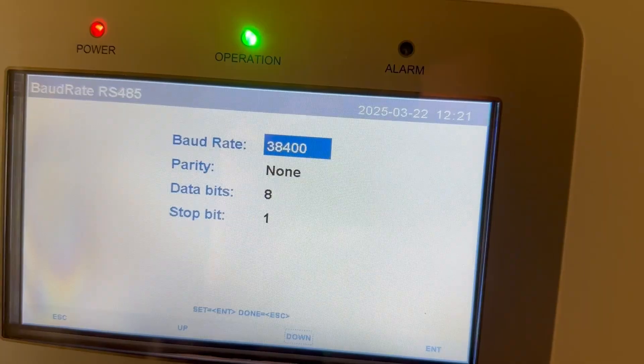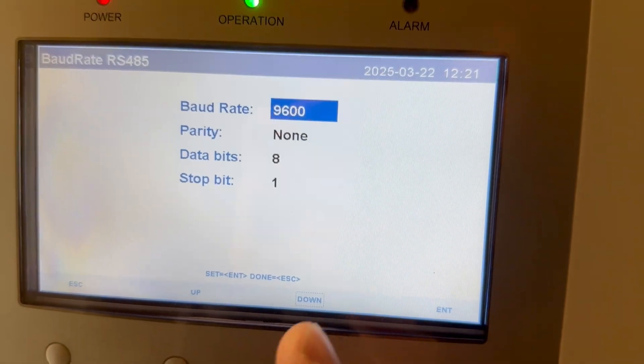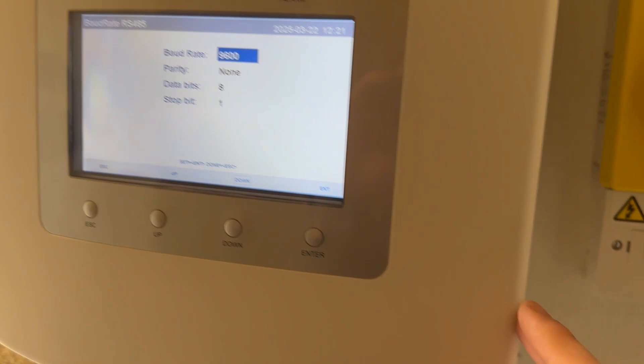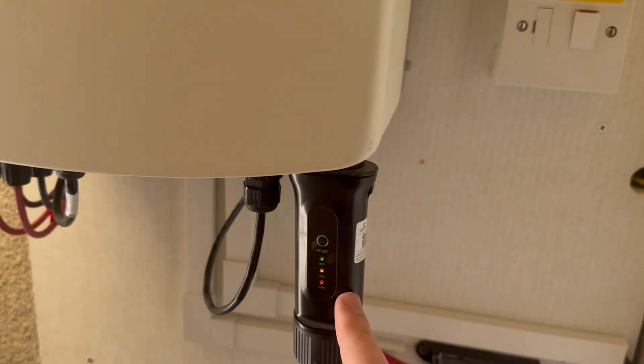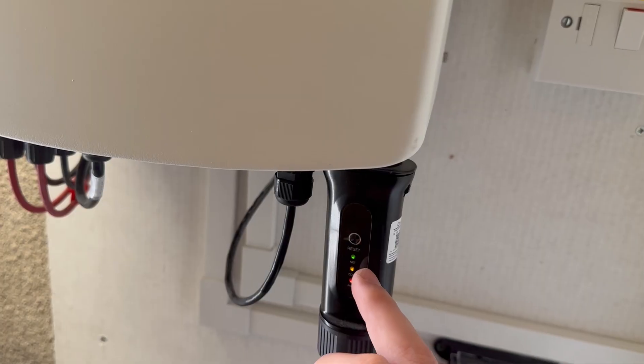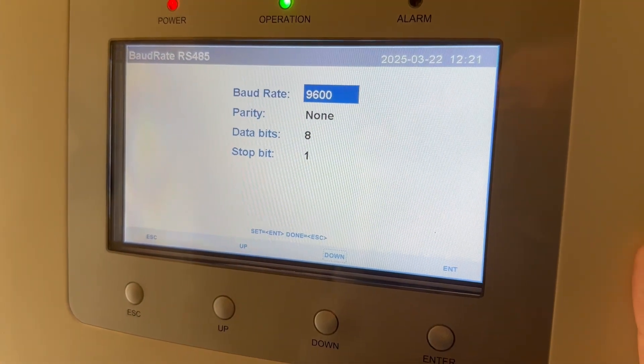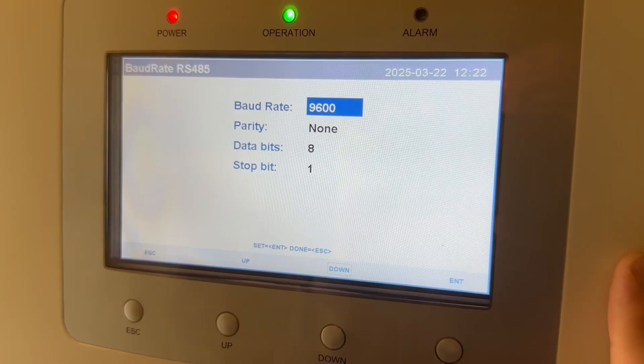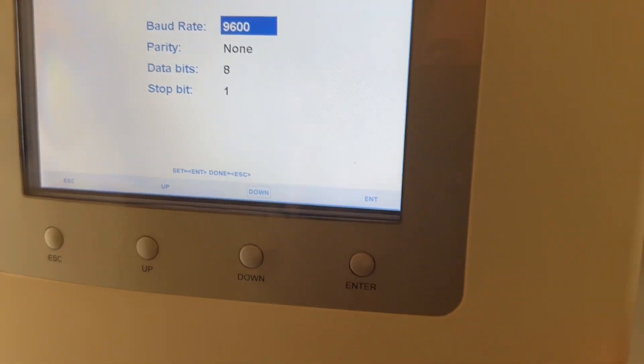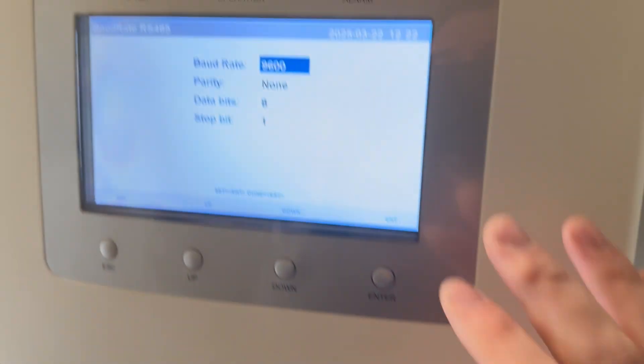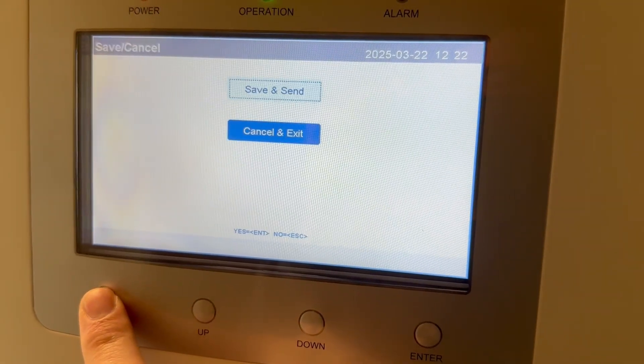As you can see, the baud rate is currently 9600. The available options are 38400, 19200, and 9600 — only three settings. 9600 is what you want. The reason is that the sensitivity level is too high at higher baud rates, and it can lose the connection and potentially damage the communication between the data logger and the inverter. I had it at 19200 for several months and it was fine, but I've heard of many people having communication difficulties, their app going offline, and apparently even destroying the data logger. So set it to 9600, press Enter, Escape, Save and Send.